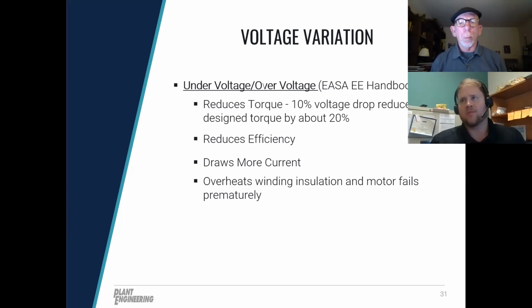One thing I wanted to cover here was some testing we completed at our lab in Raleigh. What that testing showed was a slight increase in supply voltage above rated voltage could actually lead to increased motor efficiency. During that testing, we showed that multiple 460 volt rated machines operated most efficiently at about 1.05 per unit voltage. That's about 483, 485. The same testing showed that lower voltages were detrimental to motor efficiency.